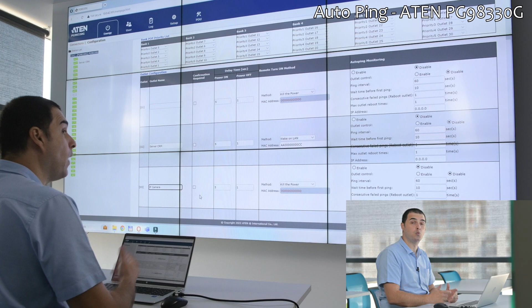Well, let's choose port number 3 and say that this is the IP camera. We enable auto ping, we enable outlet control from here, and we give the PDU the IP of the camera. Let's say the camera is on this IP, 192.168.0.150. So now what the PDU is going to do is keep pinging this IP address. When it finds that it's non-responsive, it's going to reboot that port one time. And we're going to save it.